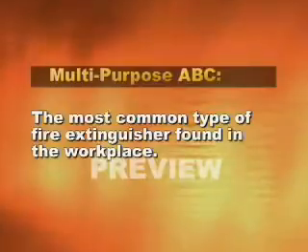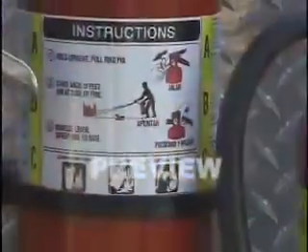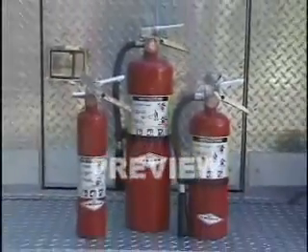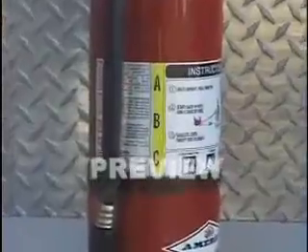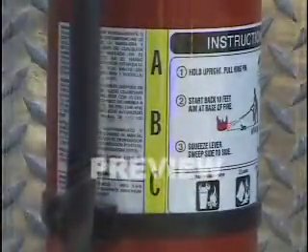The most common fire extinguishers found in the workplace have a multi-purpose ABC rating. These extinguishers are effective on Class A, B, or C fires. Special extinguishers for Class D and Class K hazards are only required where those special hazards exist.